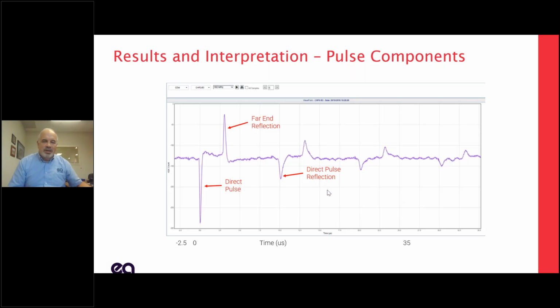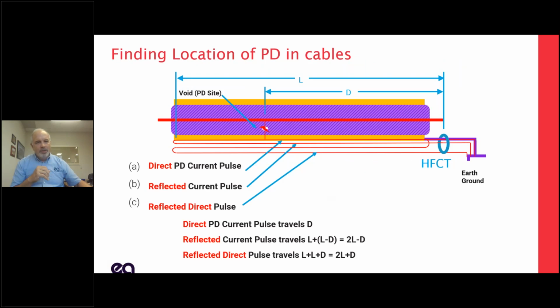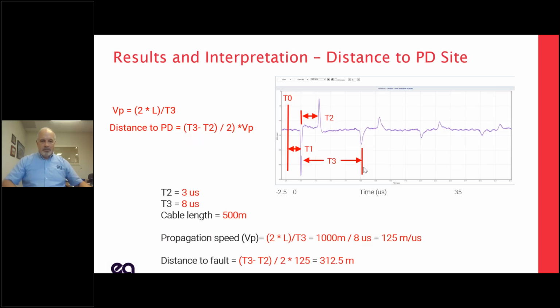Sometimes when you're doing testing, you can get a nice clean signal. This is from one of our customers in the UK. We see our first pulse, we see it reflect from the far end of the cable, we see the direct pulse reflection, beautiful picture. What we can do is use these as they reflect back and forth and the times that it takes, and we can actually calculate the distance from the HFCT to the fault.